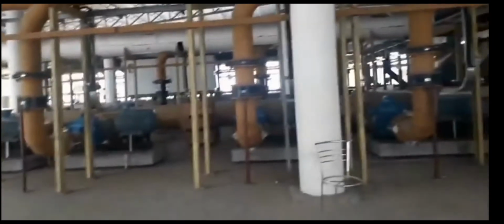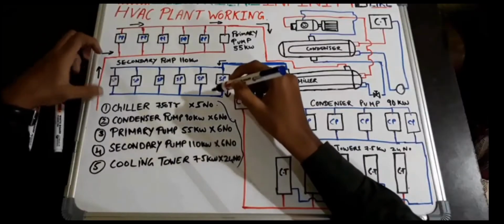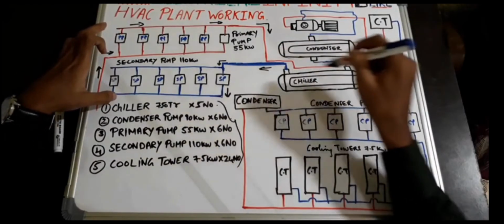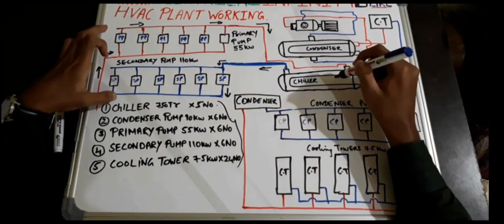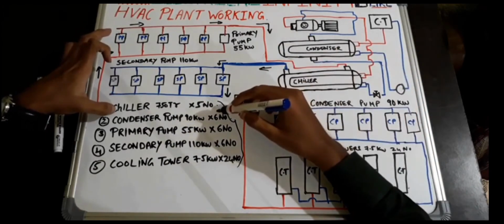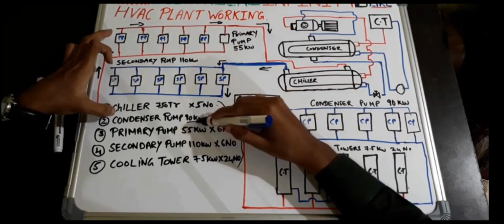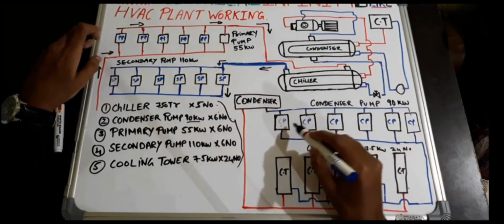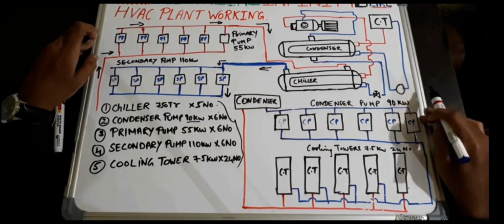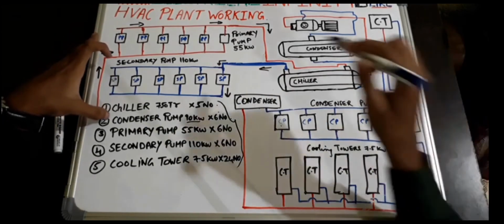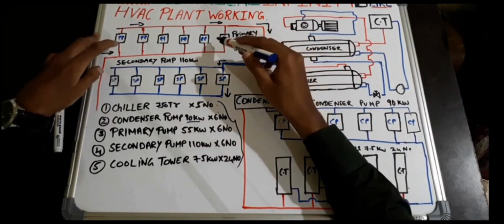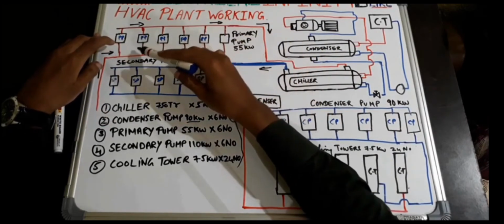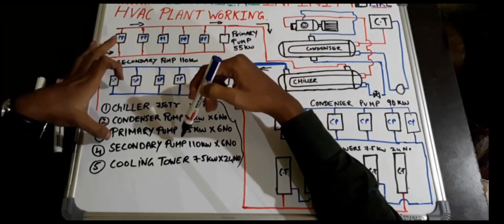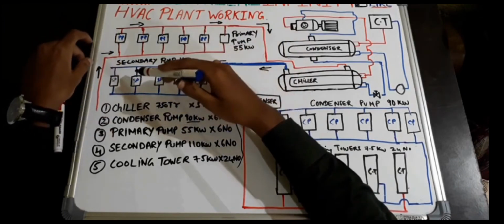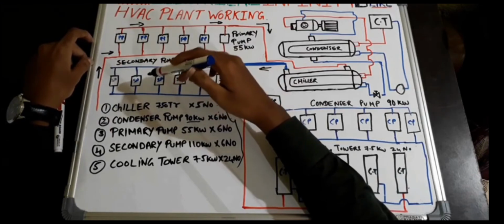Before going into the detailed explanation, first of all I am going to explain the parts we are using in this HVAC plant. So we are using 5 chillers of 750 TR. These are the chillers. We are using 6 condenser pumps, each of 90 kilowatt. Here you can see these are the condenser pumps, 6 of them, each of 90 kilowatt. After that we are using primary pumps of 55 kilowatt each, also 6 in number. After that we are using 6 secondary pumps, each of 110 kilowatt. These are the secondary pumps.